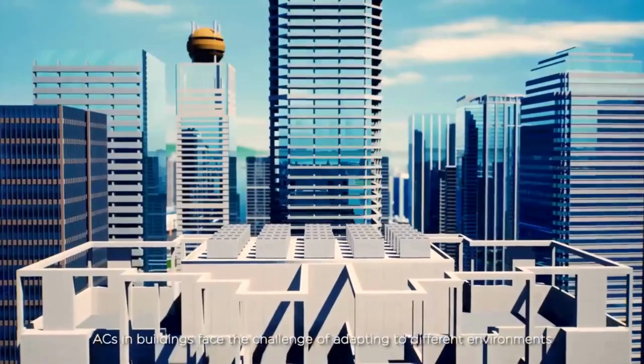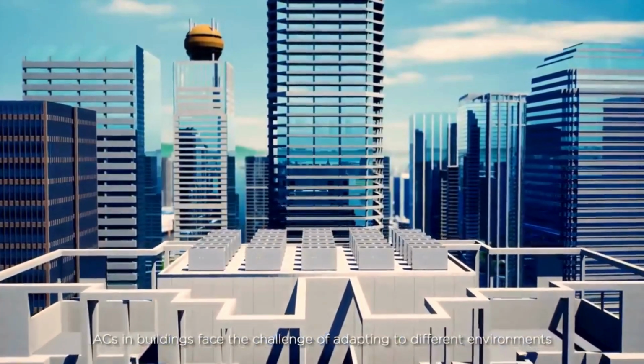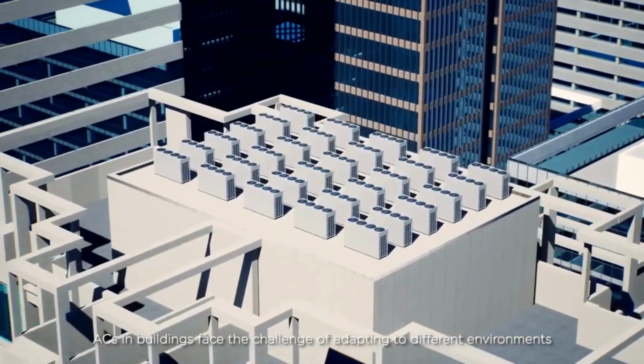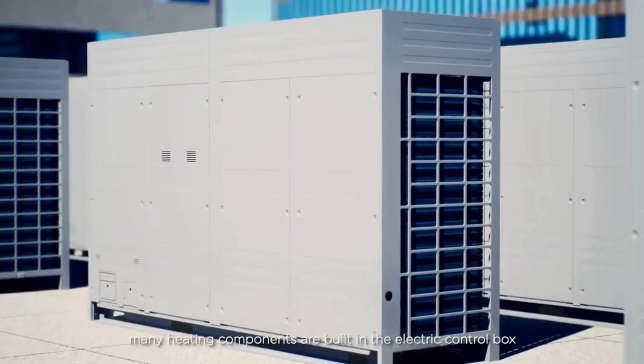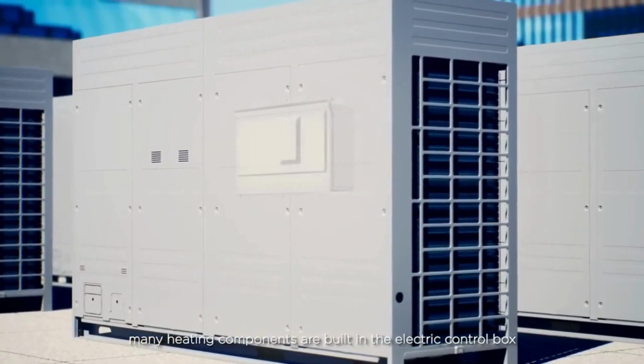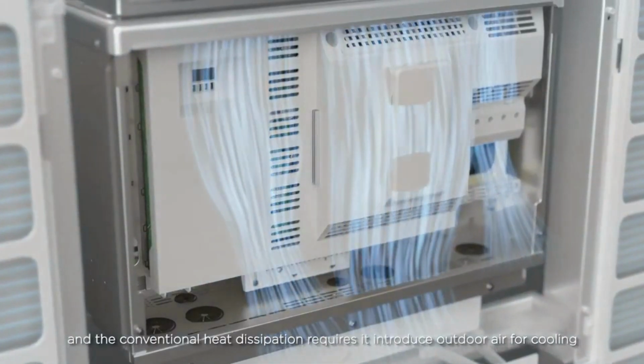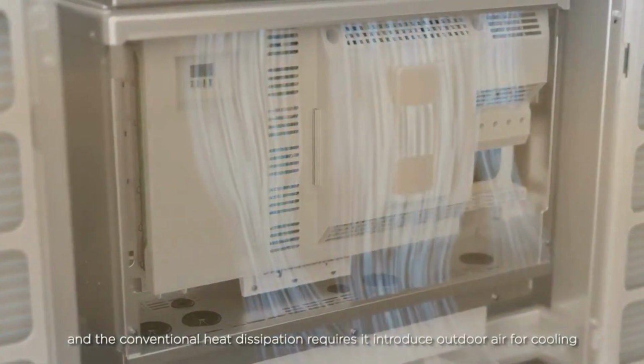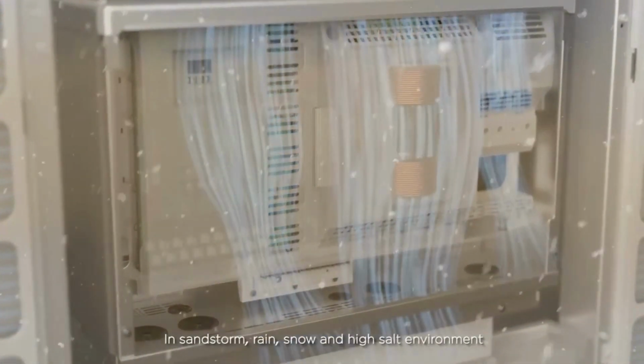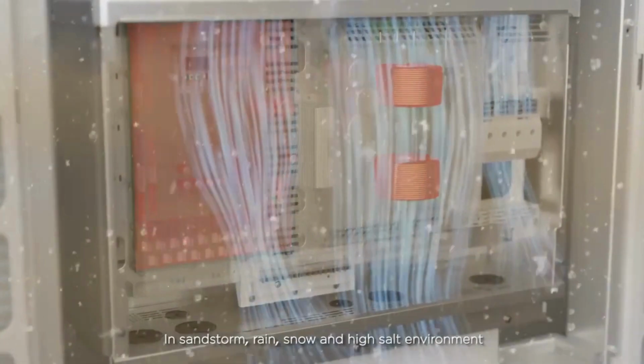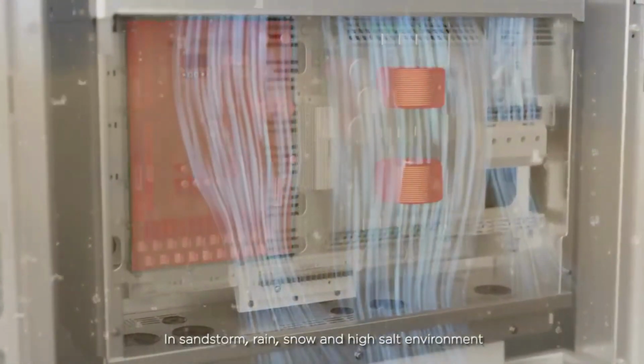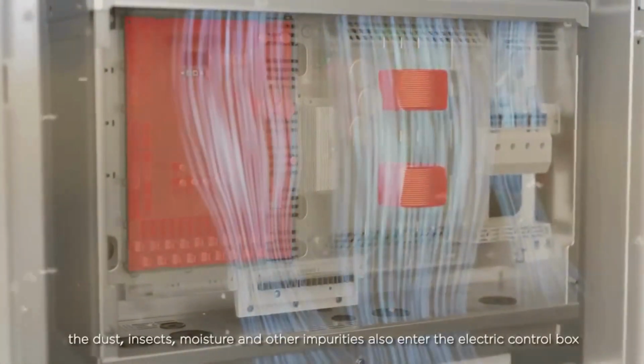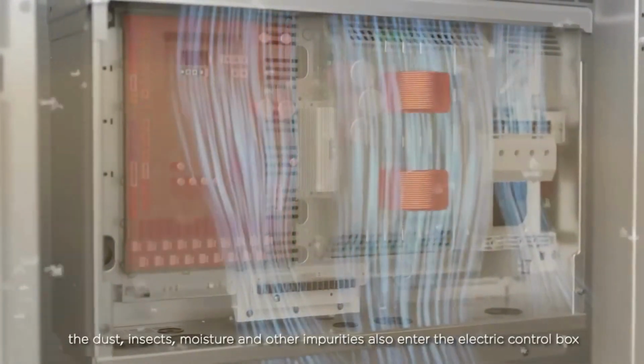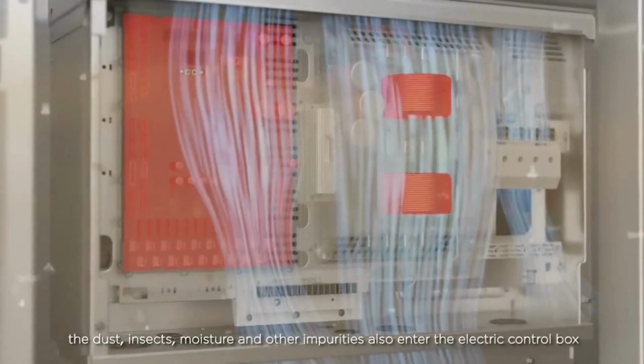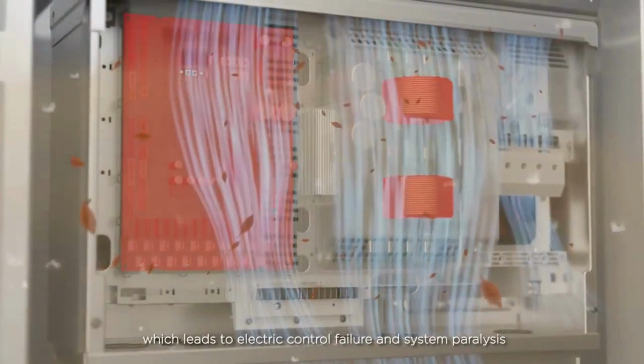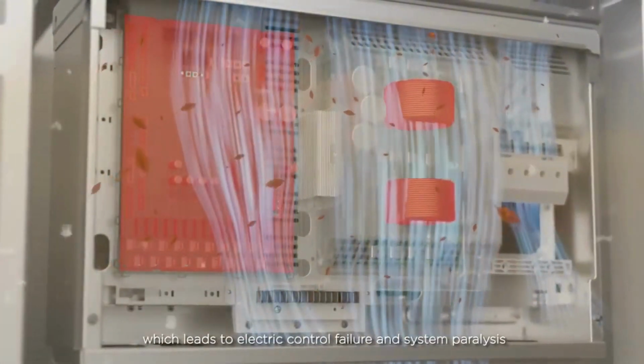ACs in buildings face the challenge of adapting to different environments. For VRFs, many heating components are built in the electric control box, and the conventional heat dissipation requires it to introduce outdoor air for cooling. In sandstorm, rain, snow, and high salt environment, with air entrance, the dust, insects, moisture, and other impurities also enter the electric control box, which leads to electric control failure and system paralysis.